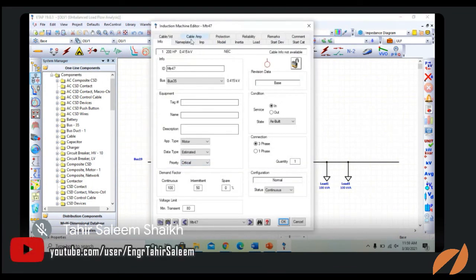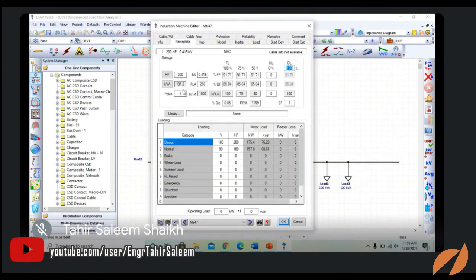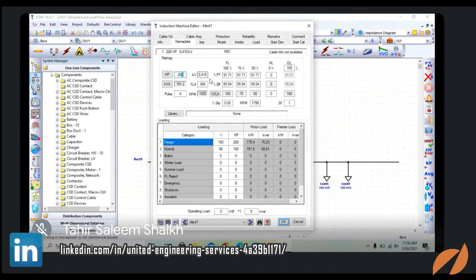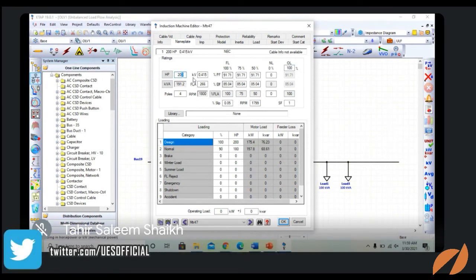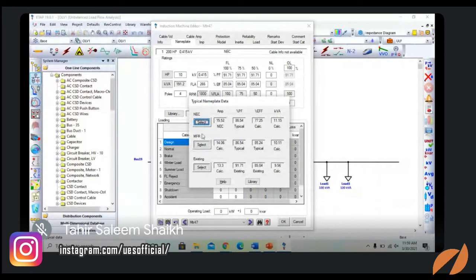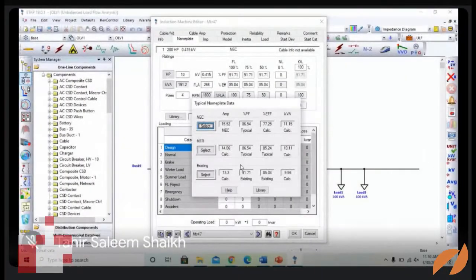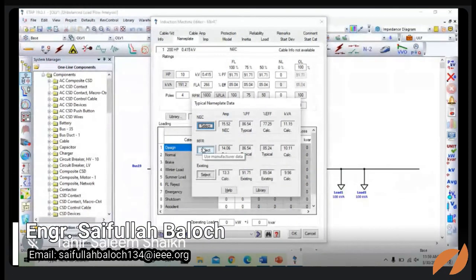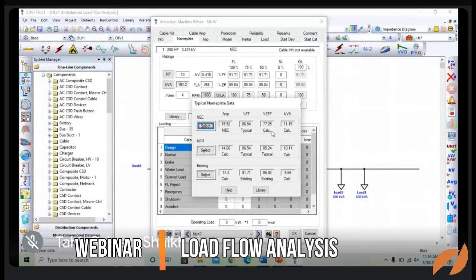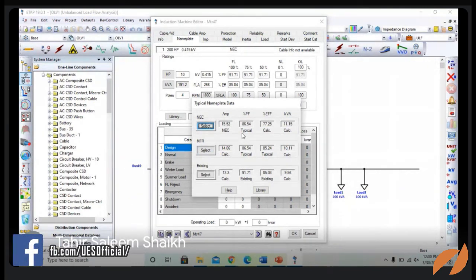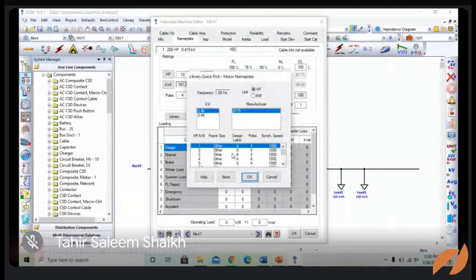Now for the motor, you can see these different nameplate ratings. You can select in horsepower. You can have full load amperage, efficiency, power factor. For example, if I change this horsepower to 10, it will allow me to select different kinds of motors, according to NEC, the existing one, and next one, this is the MFR, the user manufactured data. Whenever you change the power rating of the motor, it will give you different ratings of amperage, power factor, efficiency, kilovolt ampere. From the library you can also select the different types.